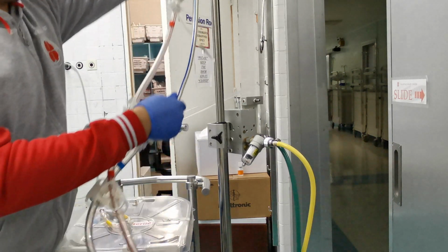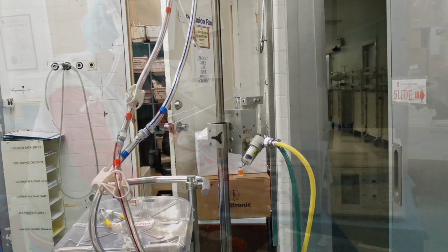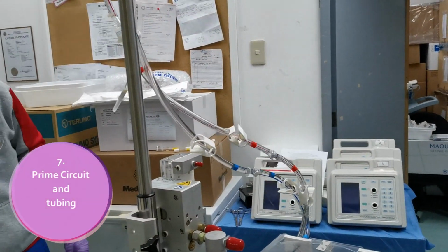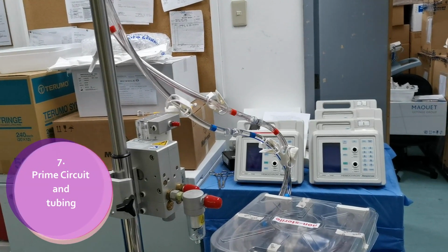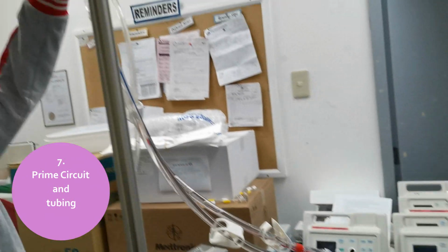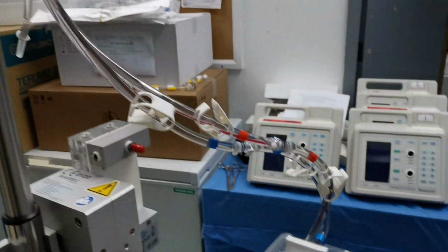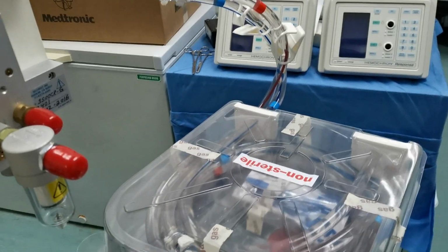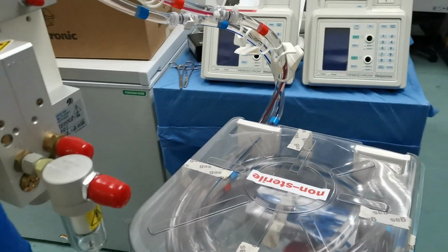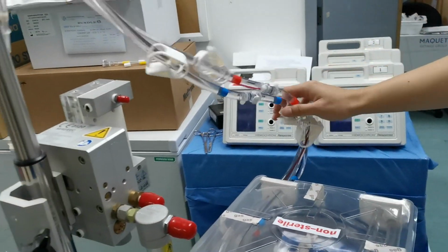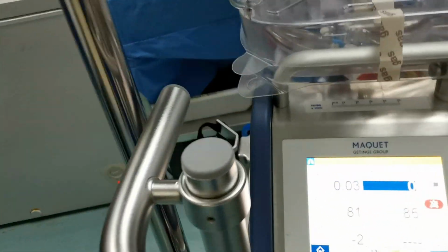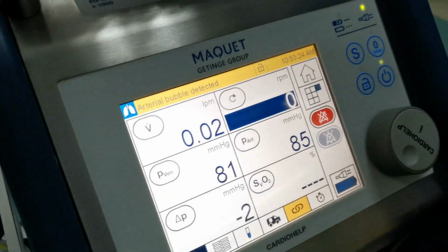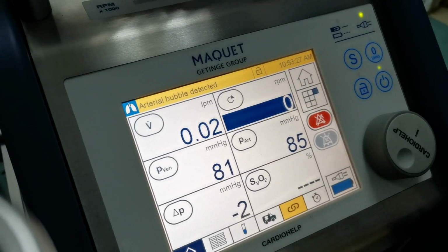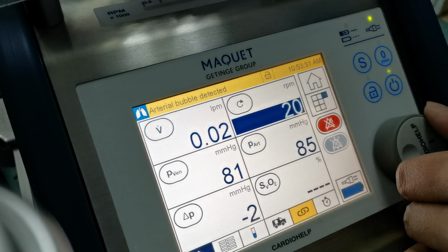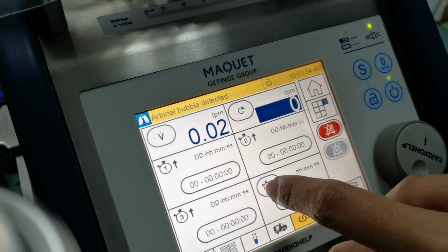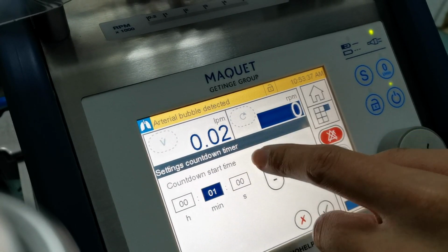During passive priming, see to it that the priming bag is adequately elevated. Unclamp the blue or venous line to initiate passive priming, thereby allowing gravity to drain the fluid across the circuit. After passive priming, run the pump at 3000 RPM for at least 2 minutes. You can actually set the timer by pressing the clock symbol in the menu bar.